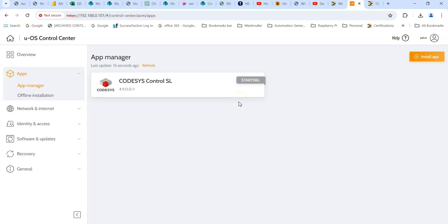You should also be aware that until you buy a Codesys runtime license, it will run in demo mode, which gives you a maximum of 2 hours usage. And if you're using things like OPC UA comms, you might find that the connection will be lost after less than 30 minutes. So you do need to purchase runtime licenses for Codesys, and it's not just one license; it depends on how big your program is, the number of fieldbus connections, etc. There are a few different parameters that define which license you need to purchase.